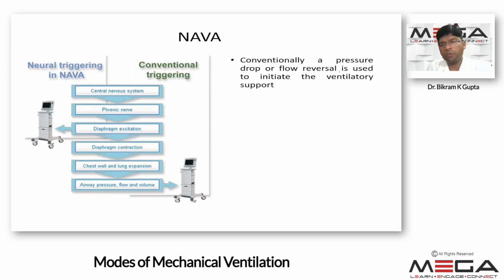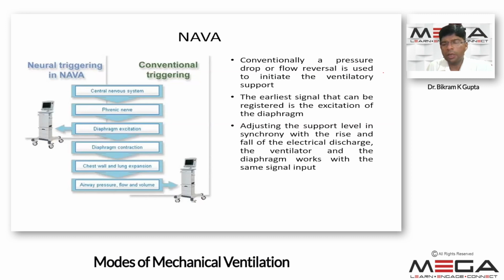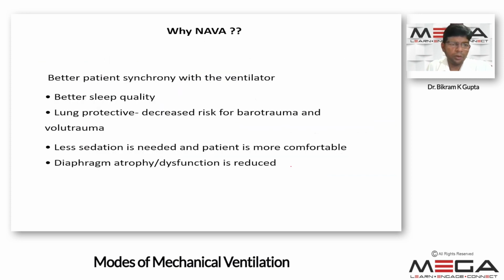Conventionally, a pressure drop or flow reversal is used to initiate ventilatory support. But in NAVA, the earliest signal that can be registered is the excitation of the diaphragm, and by adjusting the support level in synchrony with the rise and fall of the electrical discharge, the ventilator and the diaphragm work with the same signal input. So it helps with better patient-ventilator synchrony and better sleep quality. It is very helpful for lung protection because it decreases the risk of barotrauma as well as volutrauma, because it depends on diaphragm excitation or neural output. Less sedation is needed, the patient is more comfortable, and there is much less chance of diaphragm atrophy and dysfunction.